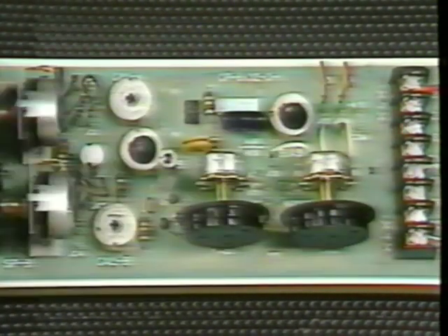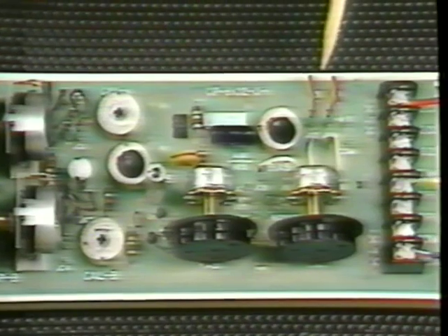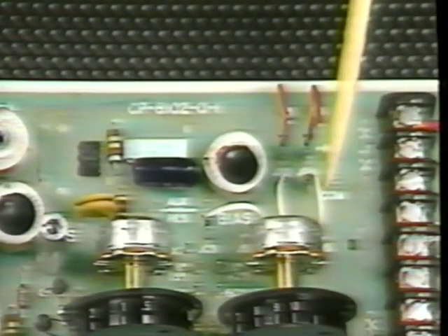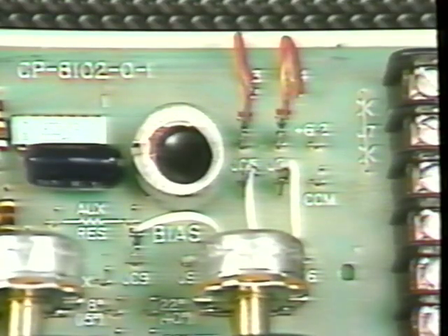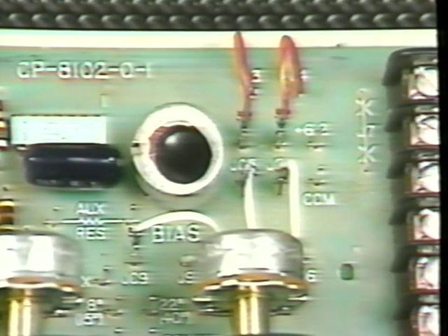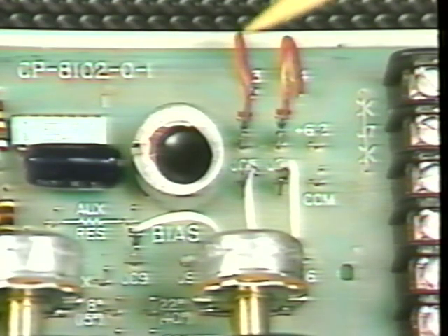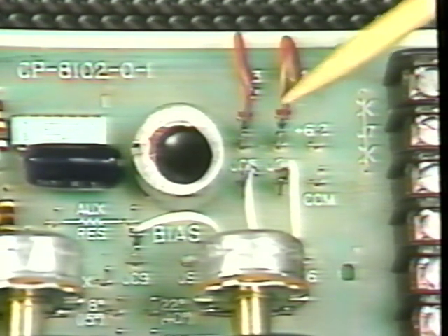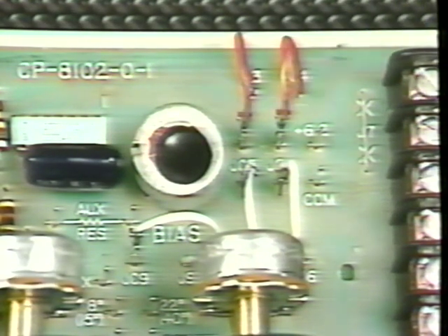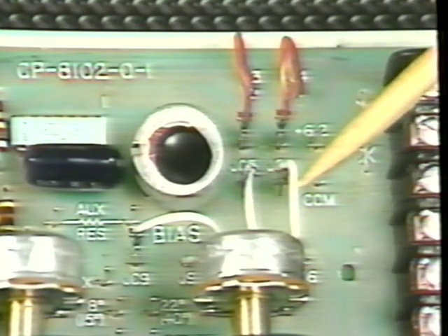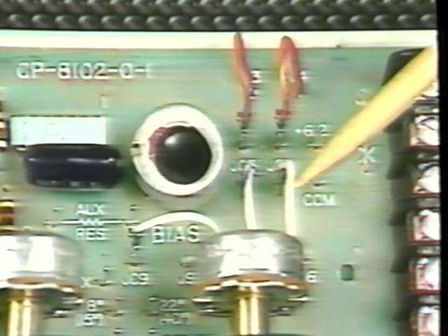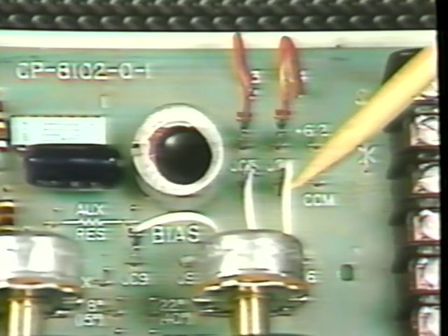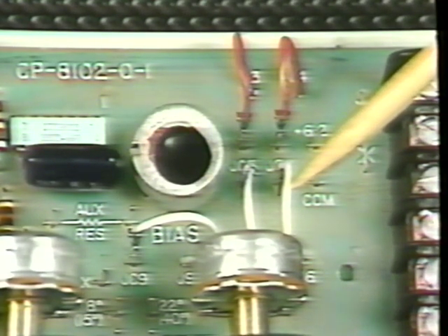Under the cover, the factory positioned action jumpers give us direct action with reverse reset. If the hot water valve or valves we're trying to control are normally open, then the factory jumper arrangement is satisfactory. With the red jumpers parallel, our controller is direct acting, and as the hot water temperature rises, our signal will rise to drive the normally open valve closed. With the second pair of jumpers also parallel, we have reverse reset. As the outside air temperature drops, that will reset the hot water set point upward.